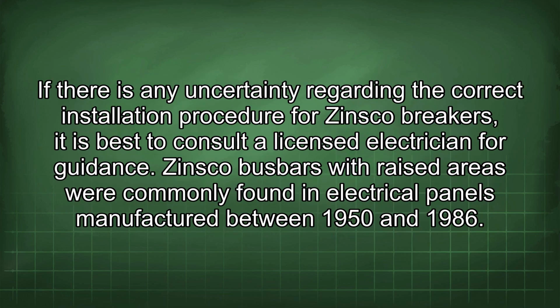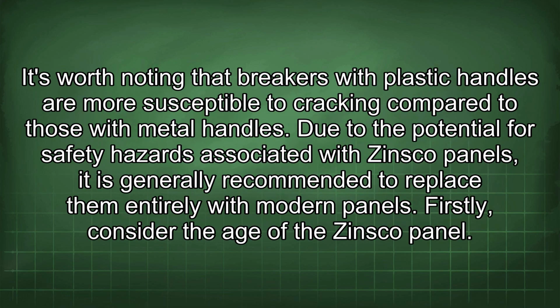If there is any uncertainty regarding the correct installation procedure for Zinsco breakers, it is best to consult a licensed electrician for guidance. Zinsco busbars with raised areas were commonly found in electrical panels manufactured between 1950 and 1986. It's worth noting that breakers with plastic handles are more susceptible to cracking compared to those with metal handles.